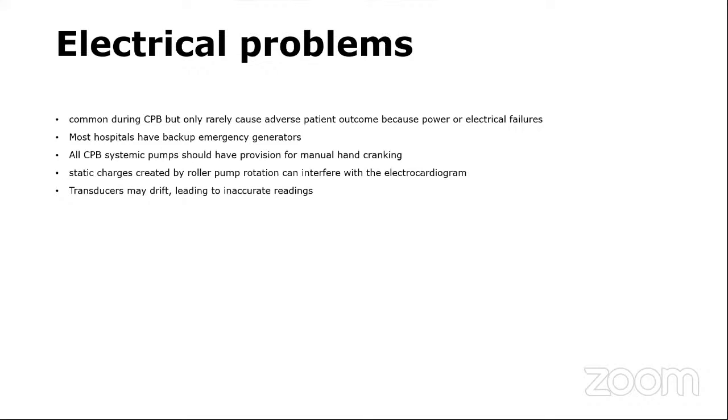And for the perfusionists, they should re-zero the transducer because it may drift during the bypass. So he should re-zero it before and also during, to have an accurate measurement parameter.